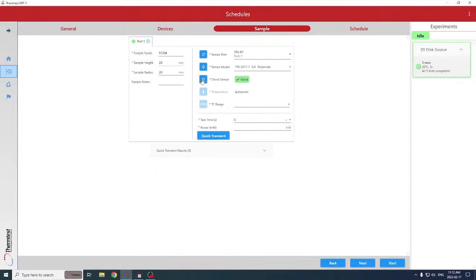Good. So all I did, you can't see in the camera angle, but I went back and just reset the sensor. So, live demo. It's kind of neat to see that step. That saves you the time of setting up a whole experiment and then starting your temperature measurements and then walking away if your sensor is not properly connected. So we didn't plan on that, but it does demonstrate the convenience of that check sensor step.